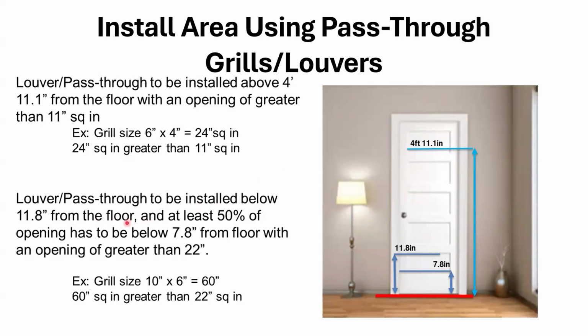And then for the bottom, the pass-through must be installed below 11.8 inches from the floor, and at least 50% of the opening has to be below 7.8 inches. So they would want that pretty much split between that. So an opening of greater than 22. For example, 10 by 6 would give us 60. 60 is greater than 22 and we'd be good to go. That's what that red line is. You can consider that undercutting the door.